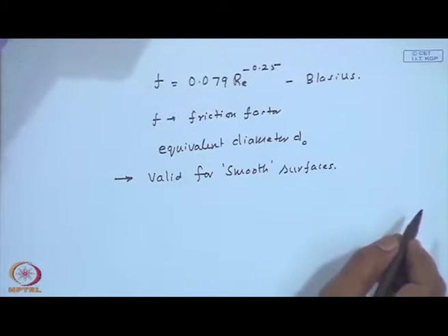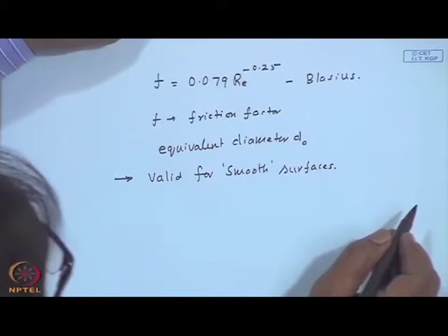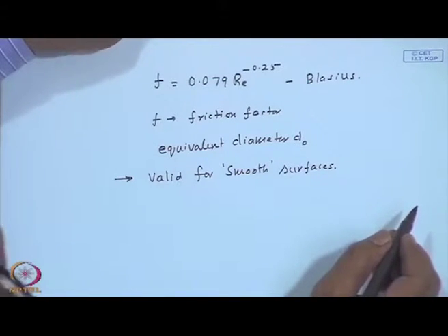So, we have methods to calculate the heat transfer coefficients in the air ducts and the friction factor, and hence calculate the pressure drop in the air duct and find out the pumping power needed and compare with the energy gain, and make sure that the energy gain is significantly more than the pumping power required.